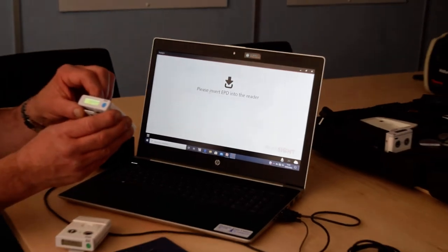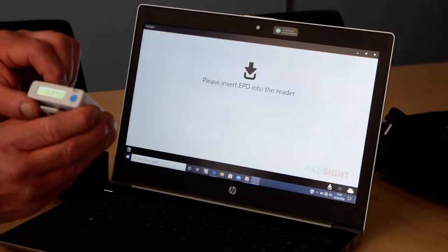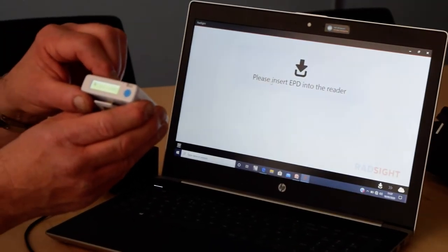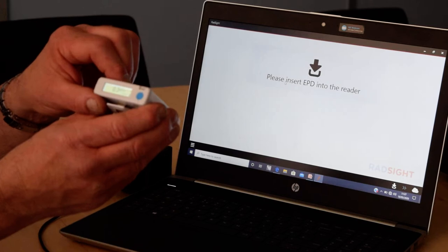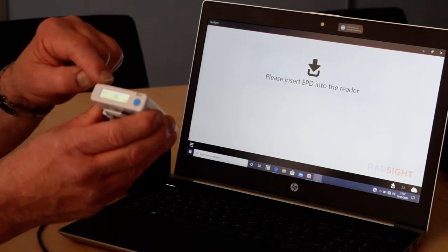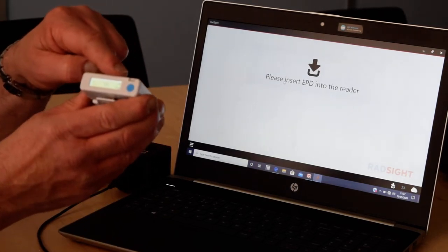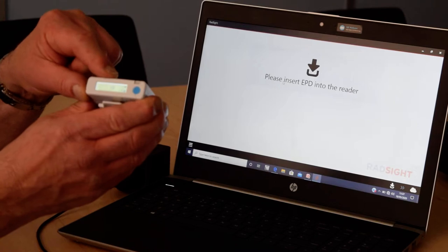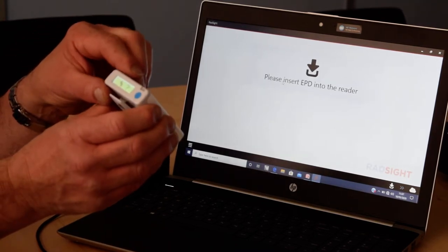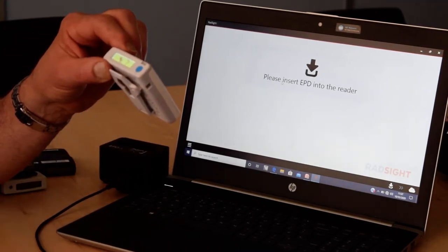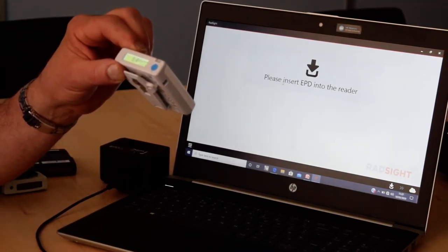It's displaying you dose, dose rate, also who it was issued to, and also a graphical display showing how much of the actual dose limit has been used up from the preset alarm. It displays both H star 10 and H star 0.07.